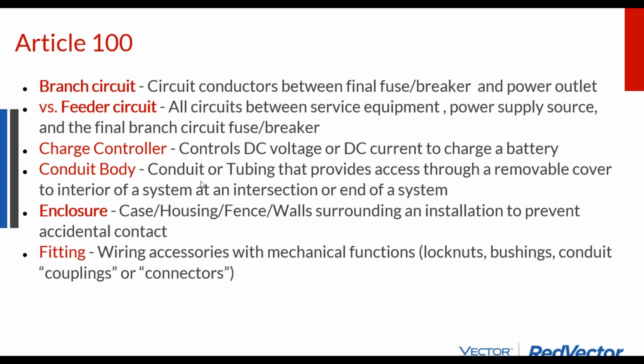Branch circuits versus feeder circuits. Feeder circuits are power supply circuits. They're dedicated for supplying power, whereas branch circuits are circuits that you're connecting loads to. And so solar and batteries, for that matter, can be connected not just right by the meter or right by the service panel, but they can be connected to any feeder circuit. They just can't be connected directly to branch circuits. So you can't have the supply and the load sharing the same wires. You have to keep the loads on their own dedicated circuits, then wire up to a service panel, and that dedicated supply line would be called a feeder circuit.